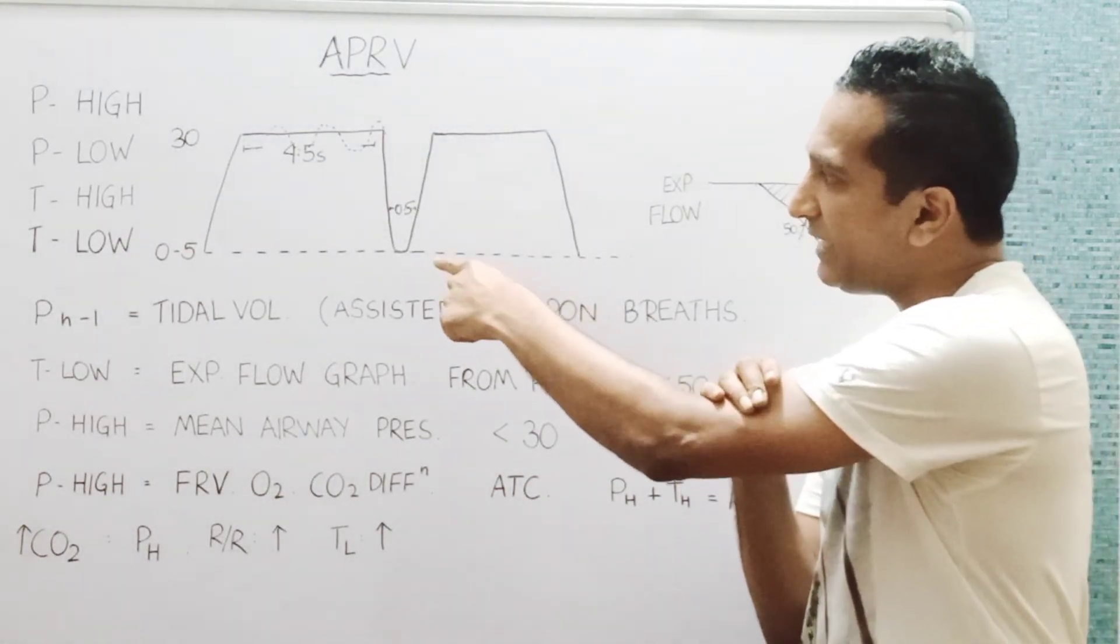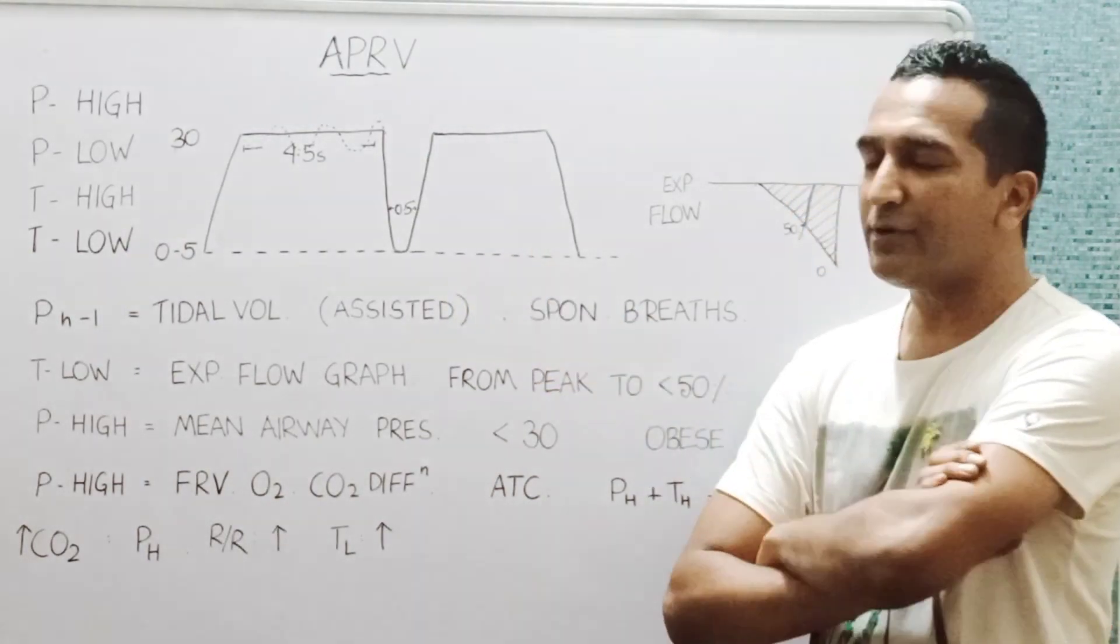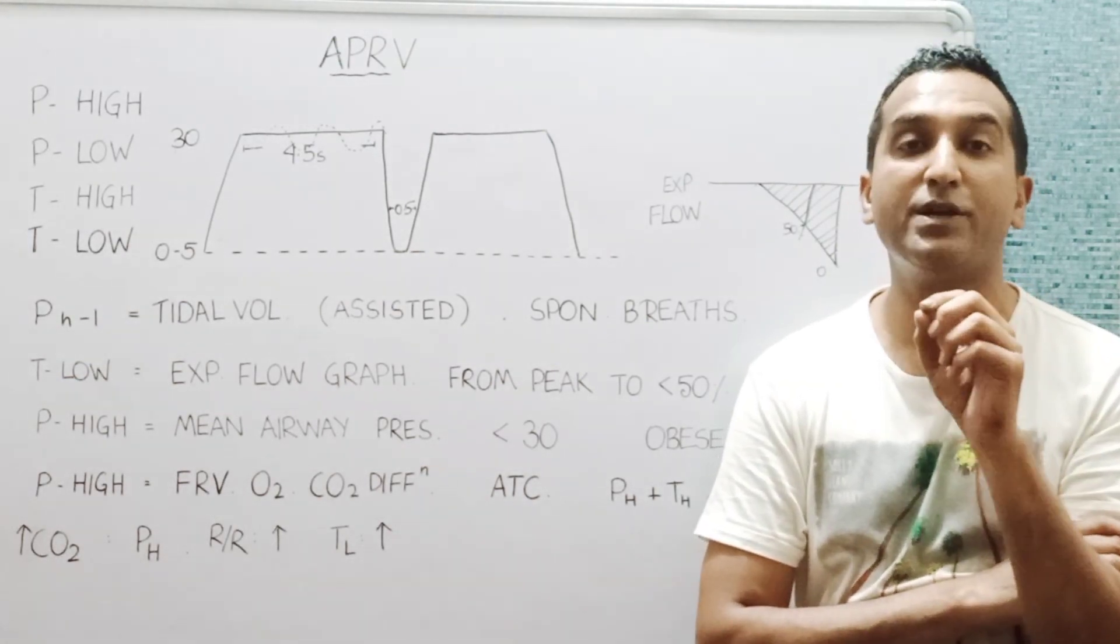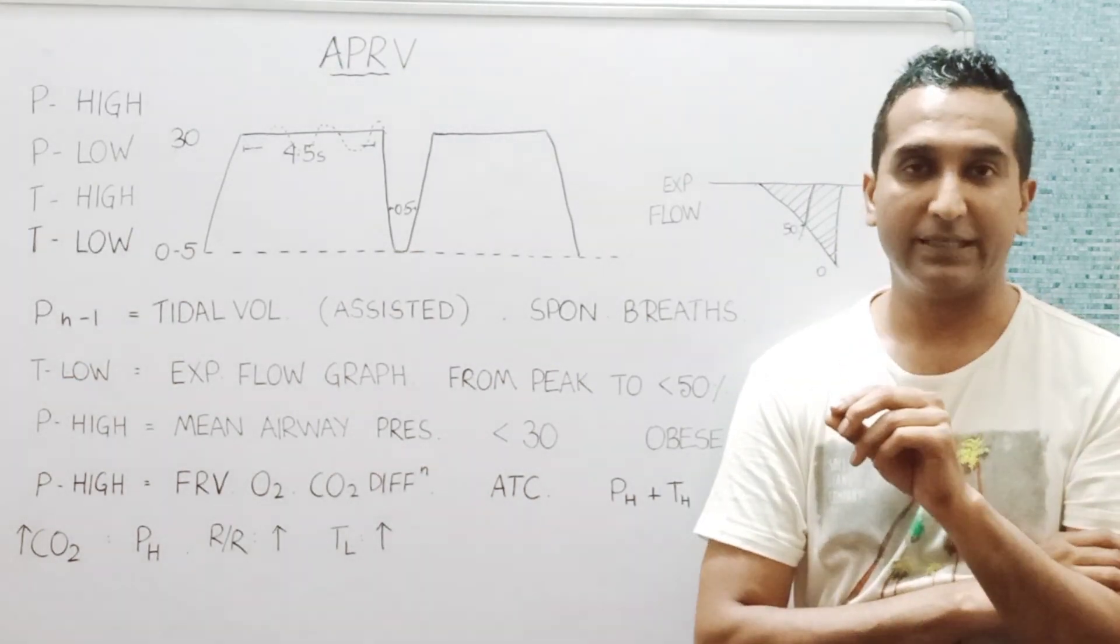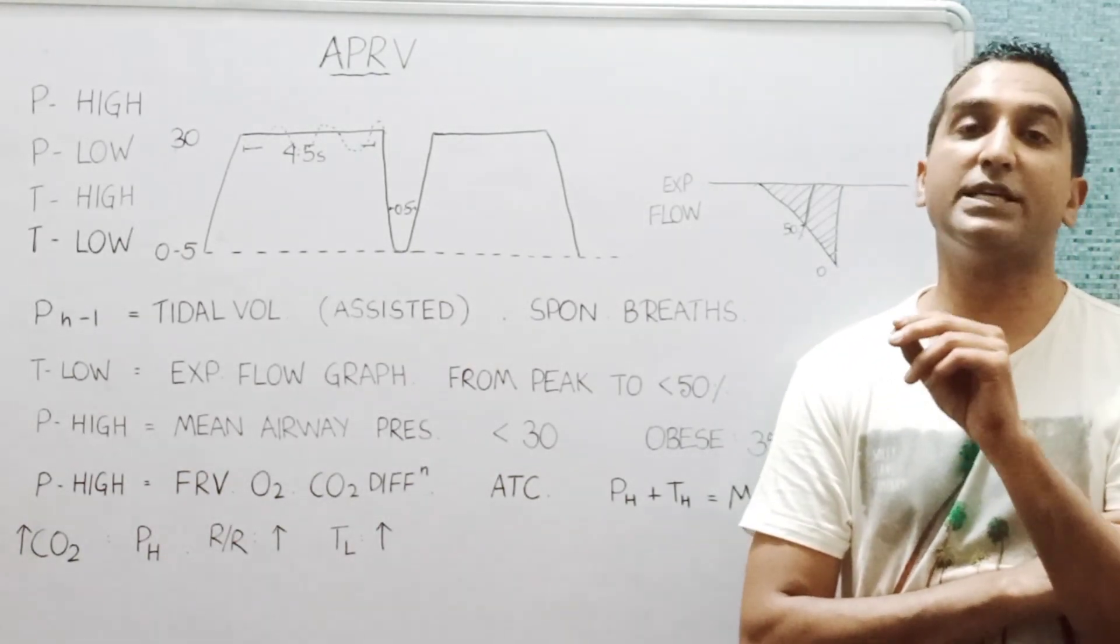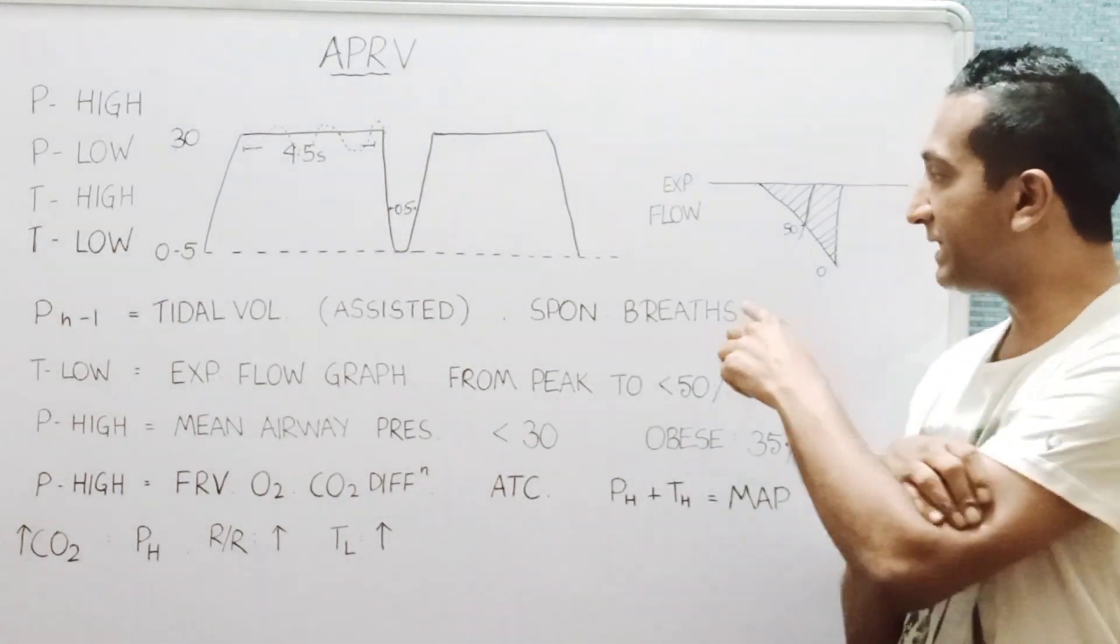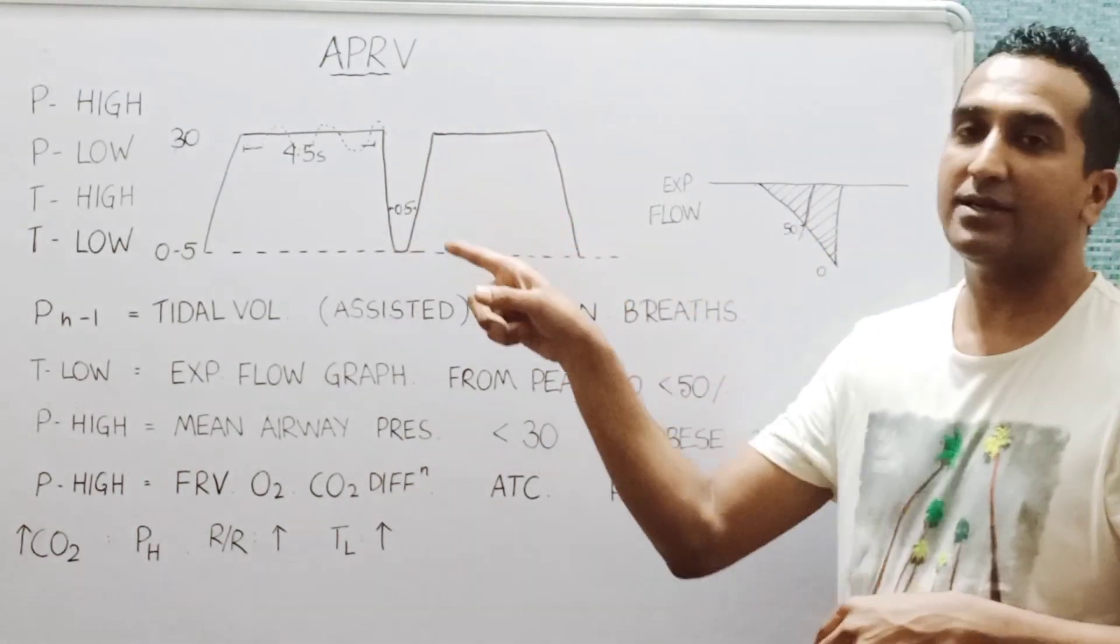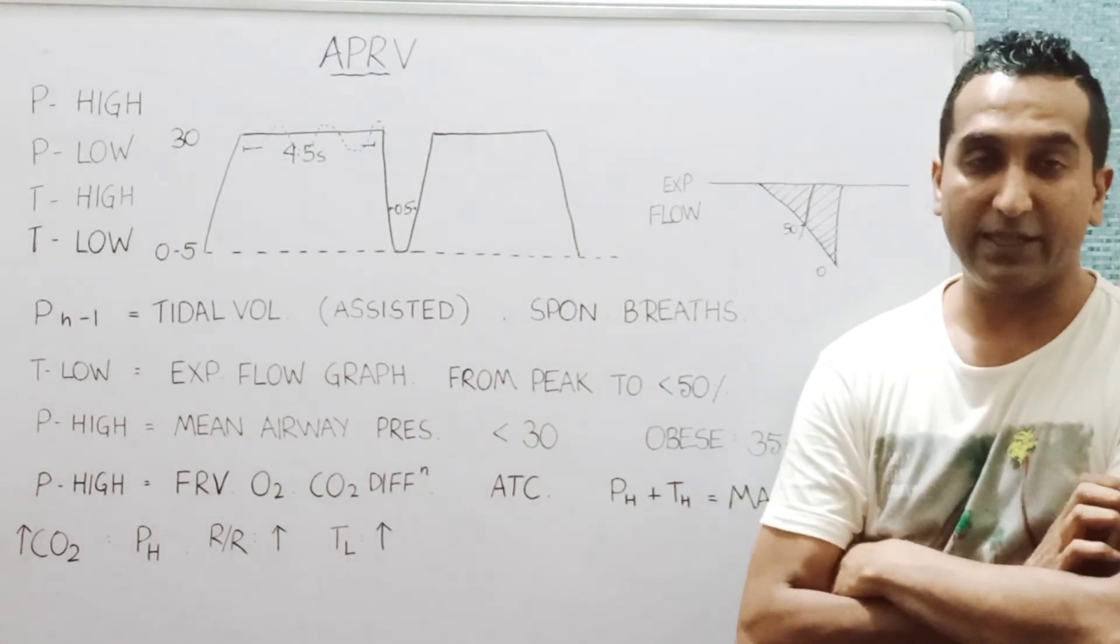When we set the T low, we set an arbitrary number of 0.5 seconds to begin with, but you should have a look at the expiratory flow graph. The expiratory flow should not drop to more than 50 percent of the peak.